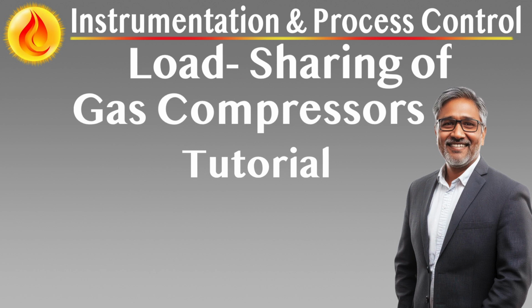Overview. The instrumentation framework for process gas compressors operating in load-sharing mode is engineered to deliver real-time coordination, precise surge protection, and balanced throughput across multiple machines. Unlike conventional compressor operation where each unit may respond independently to disturbances, the load-sharing model leverages tightly coupled sensing and control loops that synchronize compressor behavior via dynamic performance, surge, and recycle control.